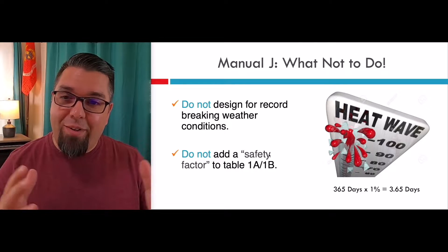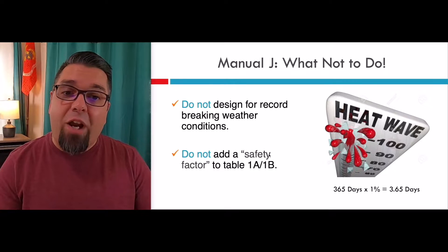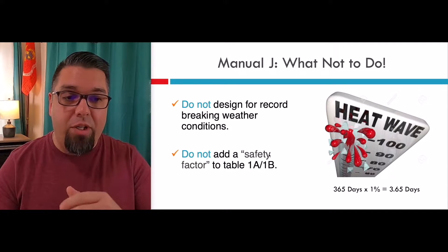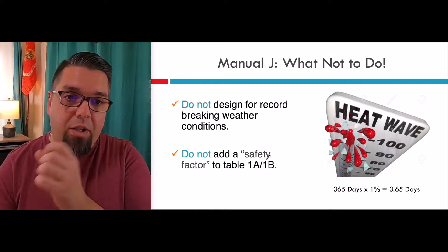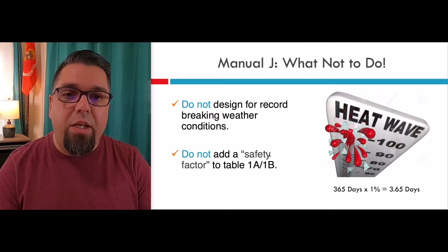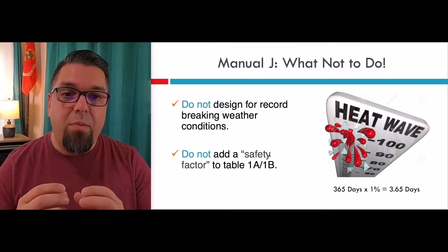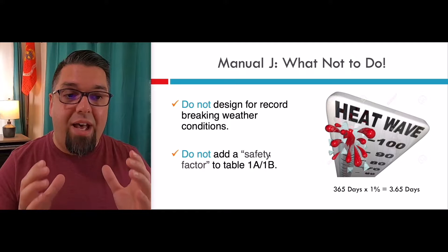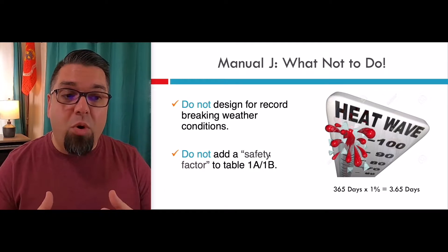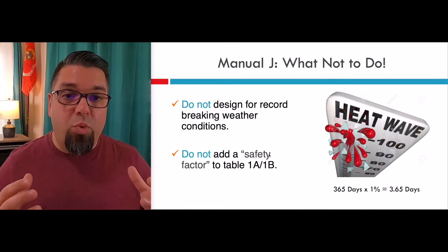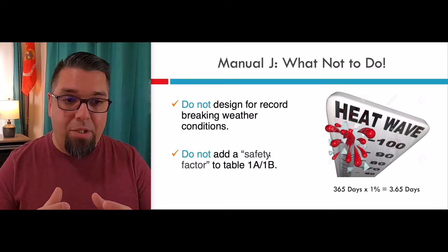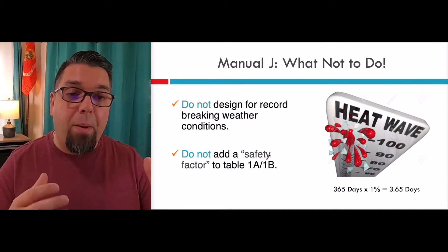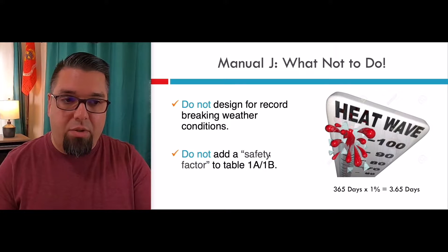This should be obvious, but I still see it out there: do not design for record-breaking weather conditions. We design using Table 1A — or Table 1B if you're in the dry part of the country — or for microclimates like Hawaii or Miami. These are different design temperatures. That's really the 99% design temperature, meaning if you add up all the hours at that temperature or above in cooling, it equals 3.65 days total. If you design around 99.9%, you're going to drastically oversize the system for no reason and have big problems under part-load conditions.